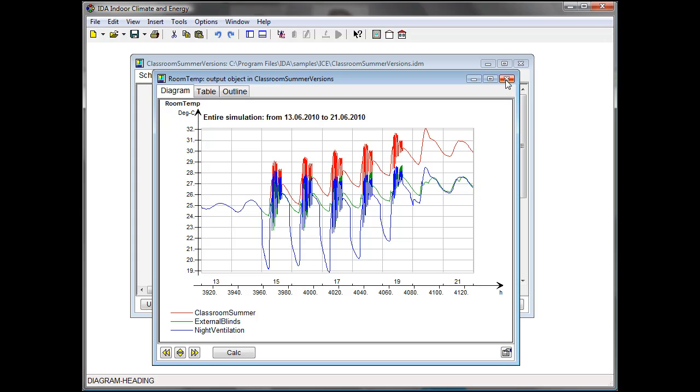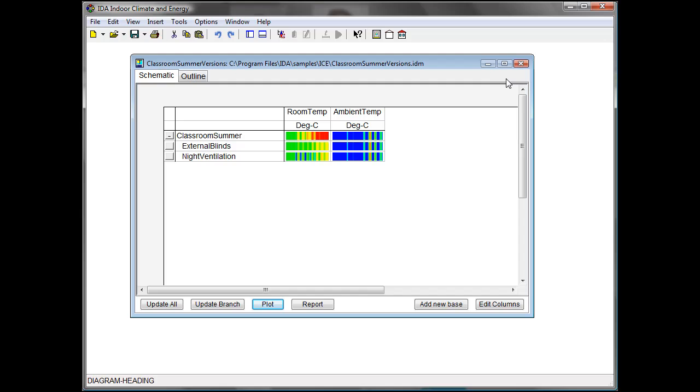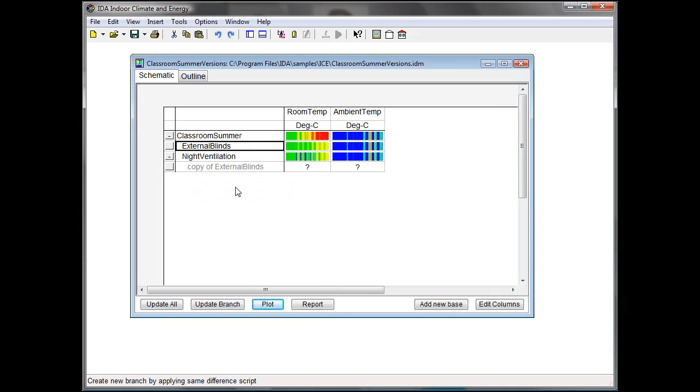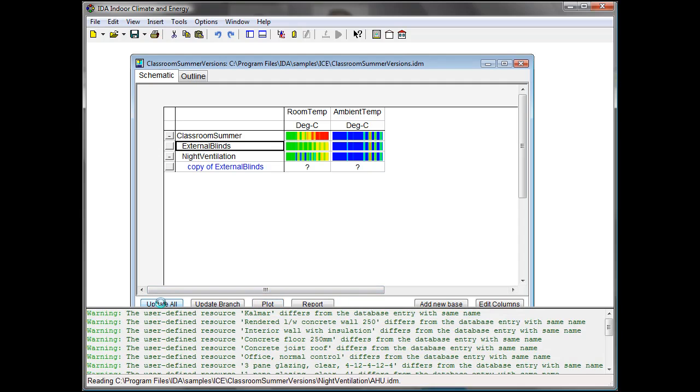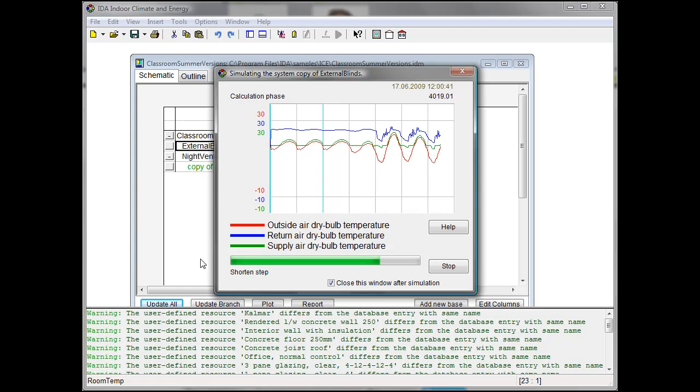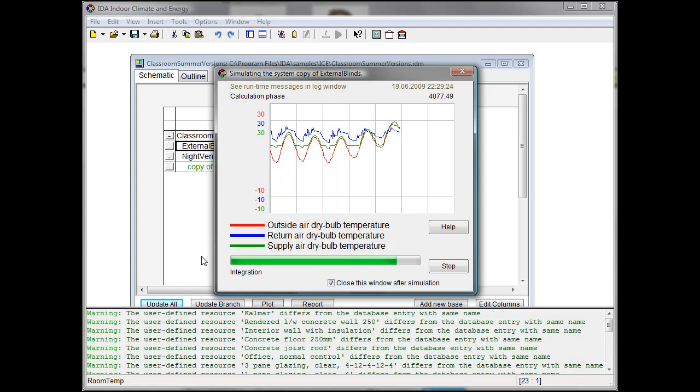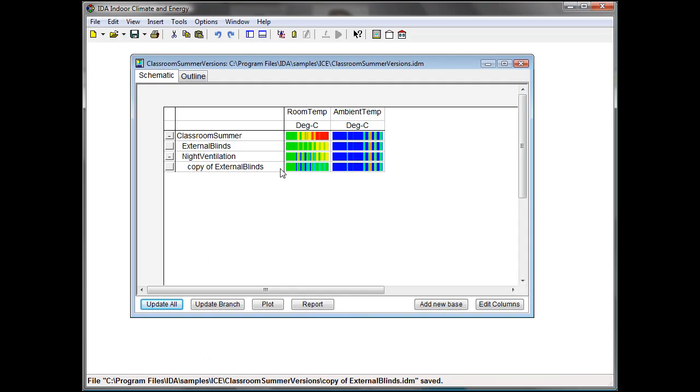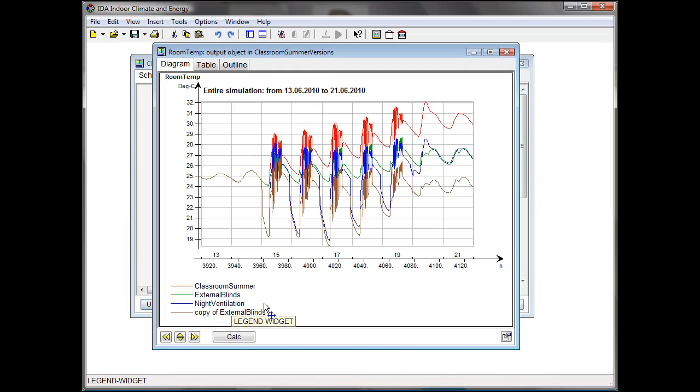To investigate the effect of the combination of both external blinds and night ventilation, we can copy the differences between two versions and get a new version with night ventilation and external blinds. Let this version get updated and look at the results, and we can see in brown our newest case where we can hold room temperature during the whole week.